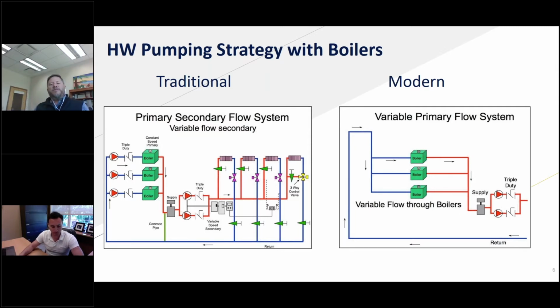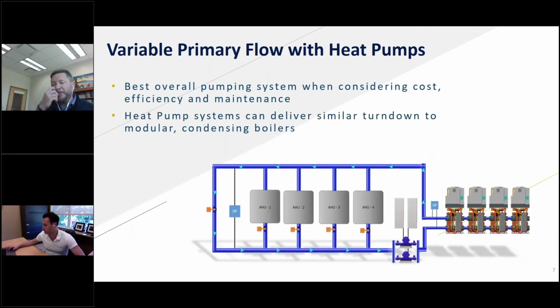The value in what we've seen happen in the industry over time with boiler technology is part of what's going to make it easier to transition. Taking existing building design and existing system design, it lends itself to being seamlessly transitioned into an air source heat pump. Whether we're utilizing multiple smaller packaged units, or a modular setup similar to a modular boiler system, we again have the ability to provide multiple units that can see flow turn down inside of a unit.